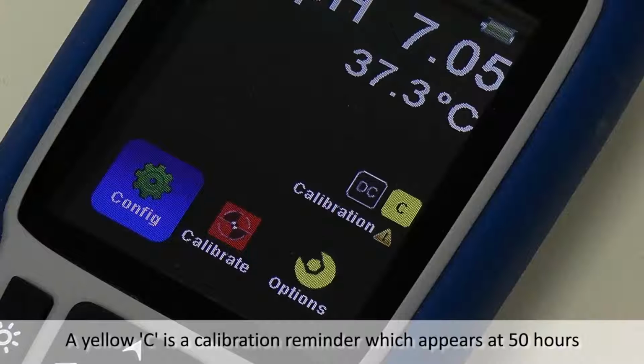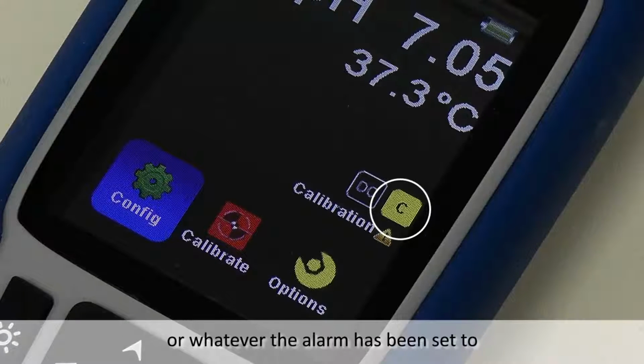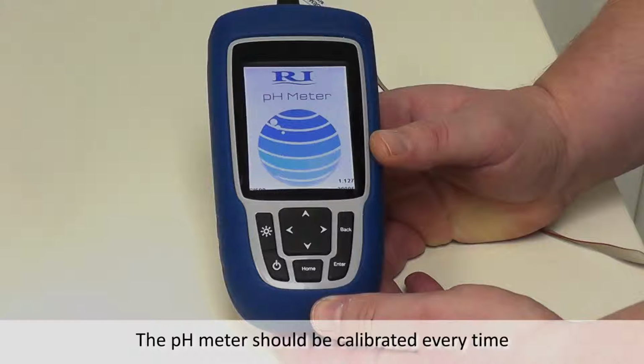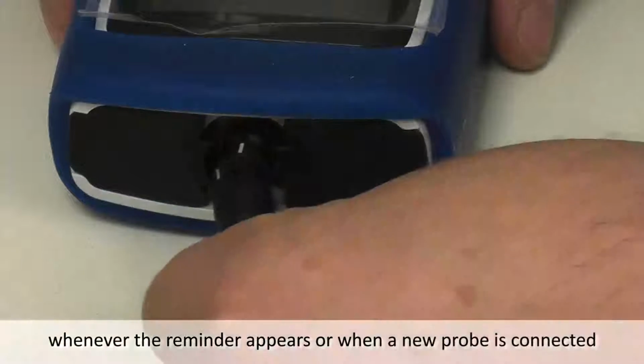A yellow C is a calibration reminder which appears at 50 hours or whatever the alarm has been set to. The pH meter should be calibrated every time it is switched off and back on, whenever the reminder appears, or when a new probe is connected.